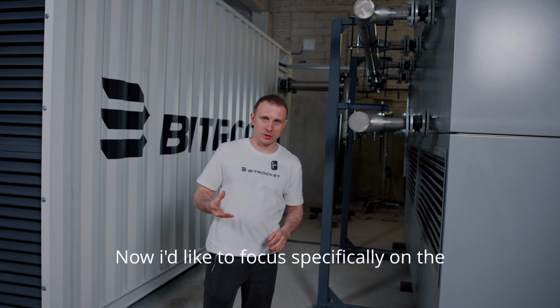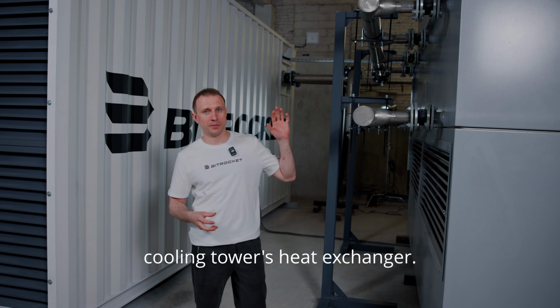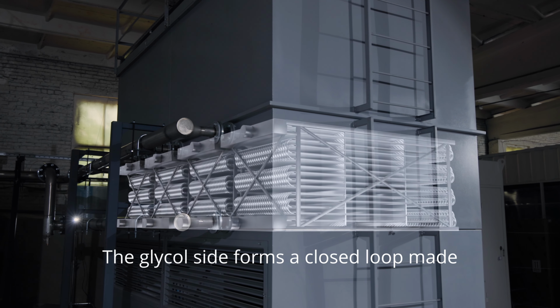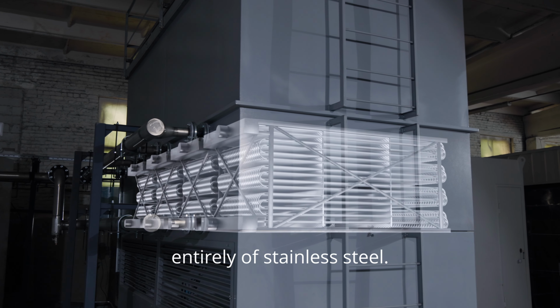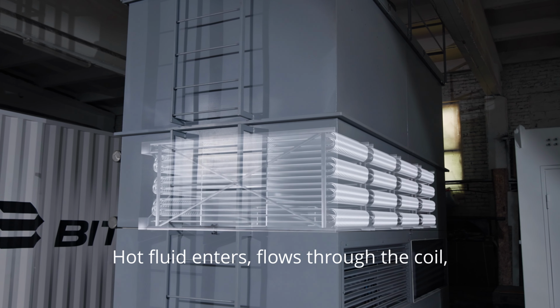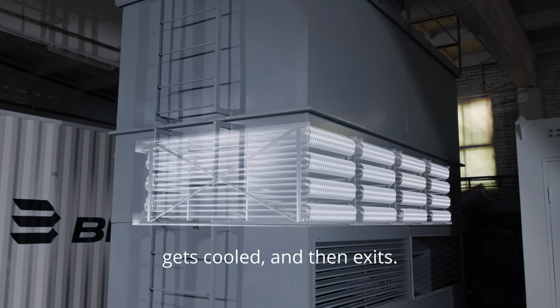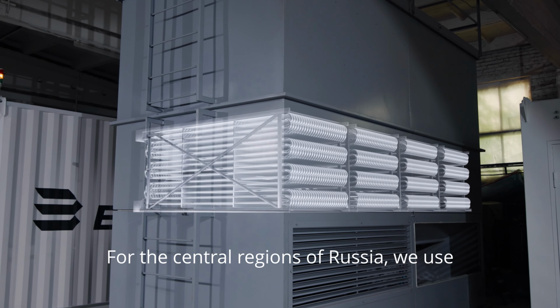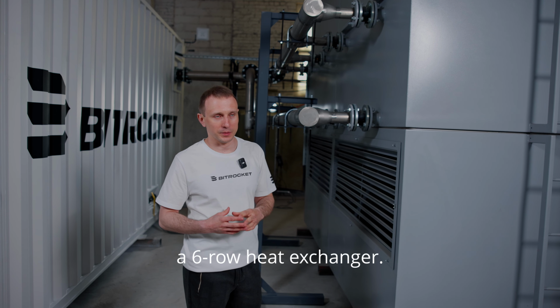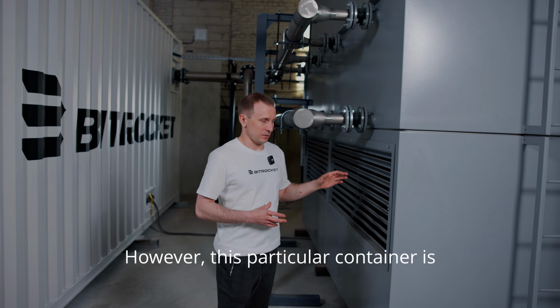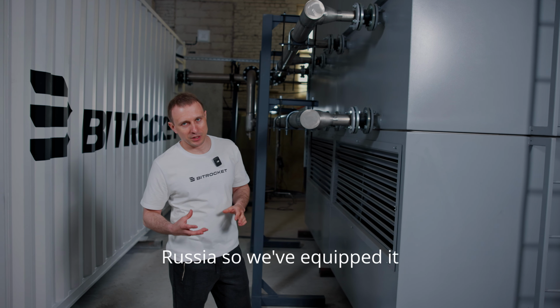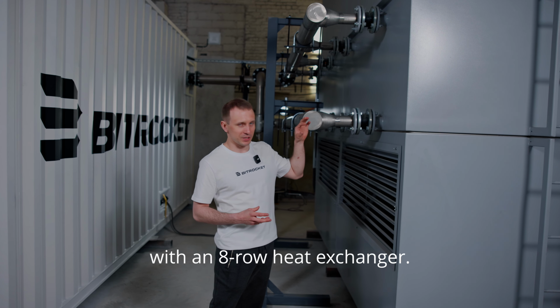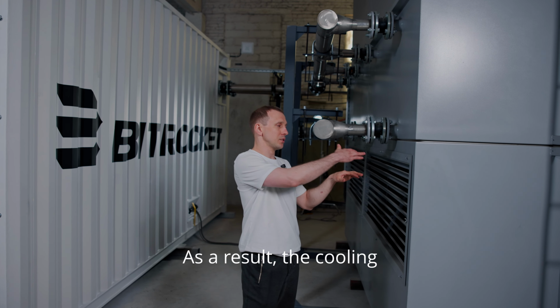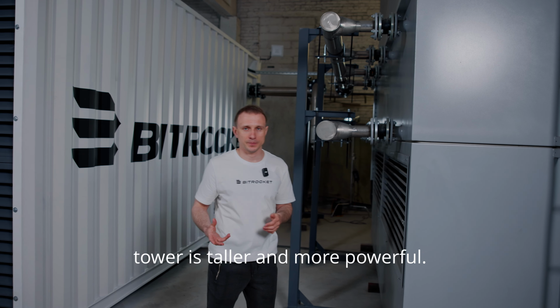Now I'd like to focus specifically on the cooling tower's heat exchanger. The glycol side forms a closed loop made entirely of stainless steel. Hot fluid enters, flows through the coil, gets cooled, and then exits. For the central regions of Russia, we use a 6-row heat exchanger. However, this particular container is destined for southern Russia, so we've equipped it with an 8-row heat exchanger. As a result, the cooling tower is taller and more powerful.